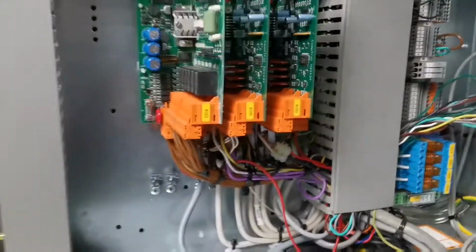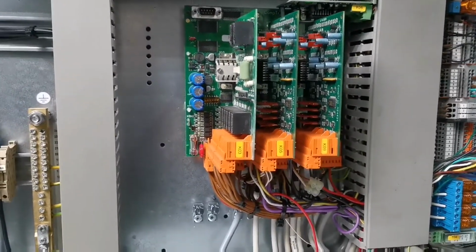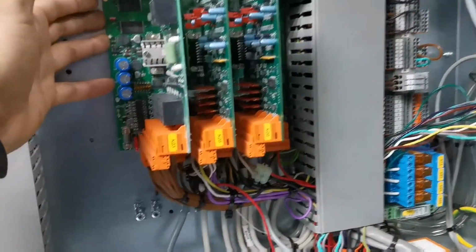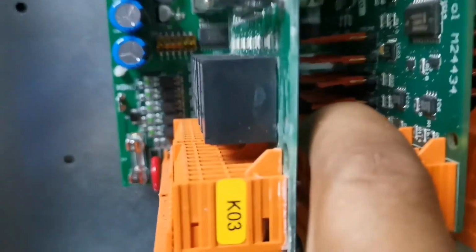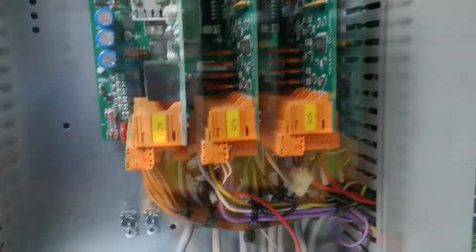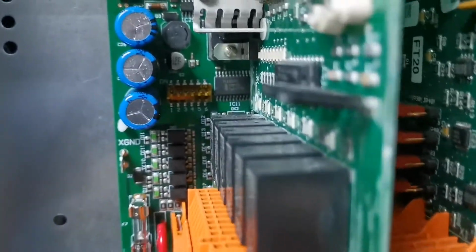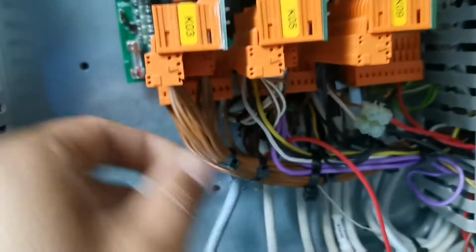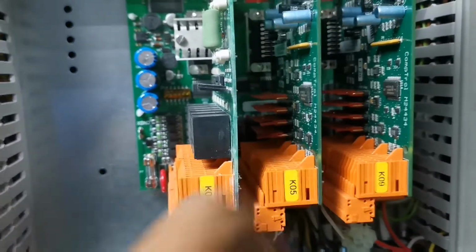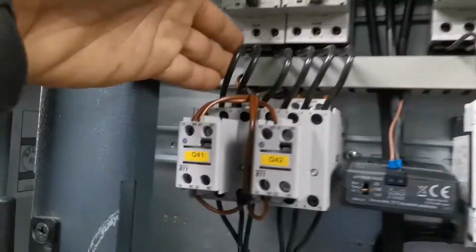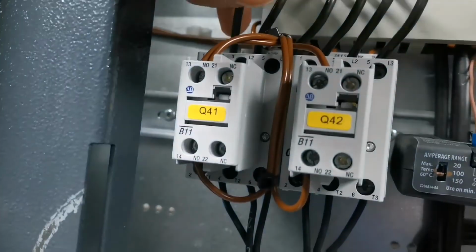We then contacted tech support, and I suspected that we had an issue on the board because I don't know if you'll be able to see, but there's a relay right there which is D02. Should be able to see it right there. Yep. So that's your digital output 2, which basically loops your circuit and calls for cooling. That's when the system's calling for cooling. At that stage only you will get your 24 volts on your Q41 contactor, which is for circuit 1.